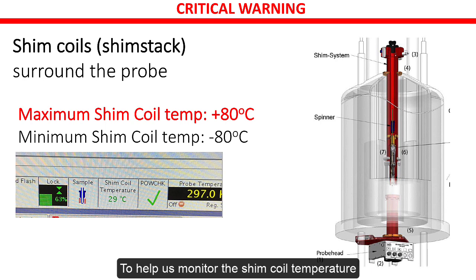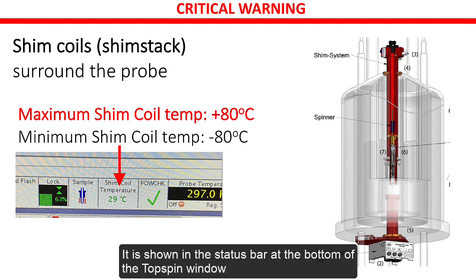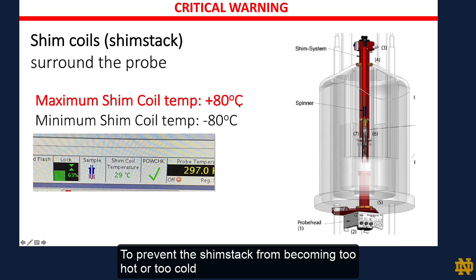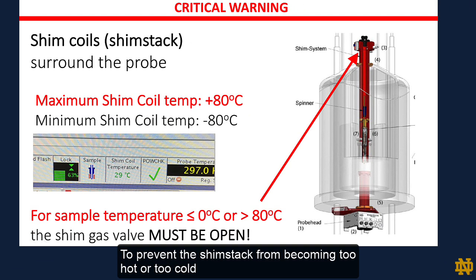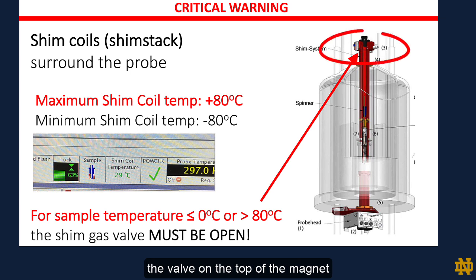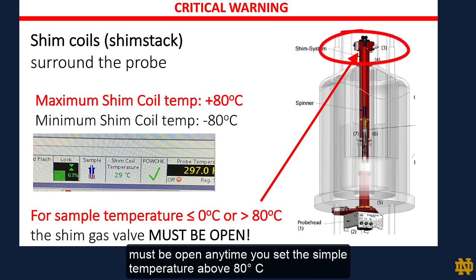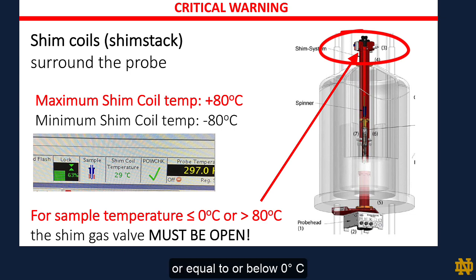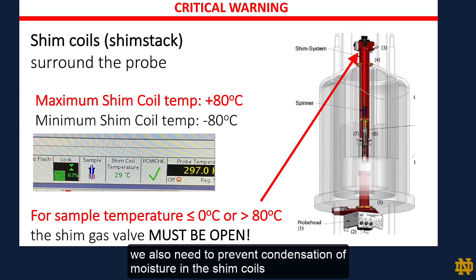To help us monitor shim coil temperature, it is shown in the status bar at the bottom of the TopSpin window. To prevent the shimstack from becoming too cold or too hot, we are passing a dry nitrogen gas through the shim coils. The valve on the top of a magnet must be open anytime you set sample temperature above 80 degrees C or equal or below 0 degrees C. The lower limit is 0 degrees because we also need to prevent condensation of moisture in the shim coils.